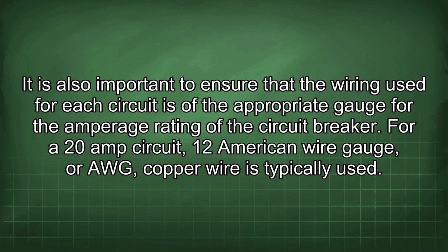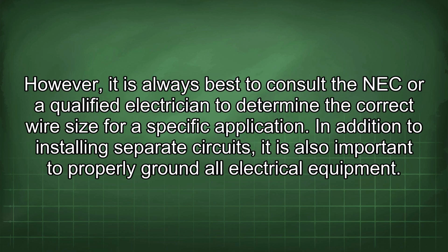For a 20-amp circuit, 12 American wire gauge, or AWG, copper wire is typically used. However, it is always best to consult the NEC or a qualified electrician to determine the correct wire size for a specific application. In addition to installing separate circuits, it is also important to properly ground all electrical equipment.